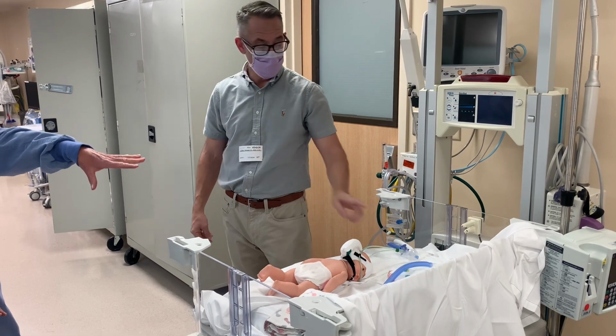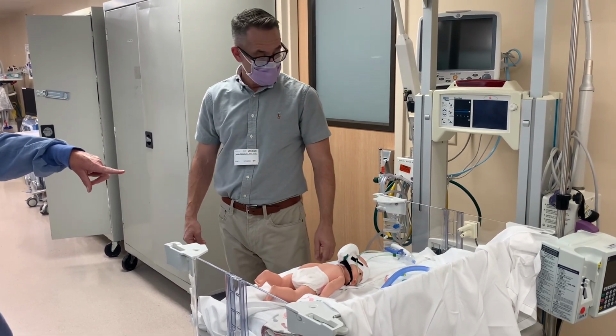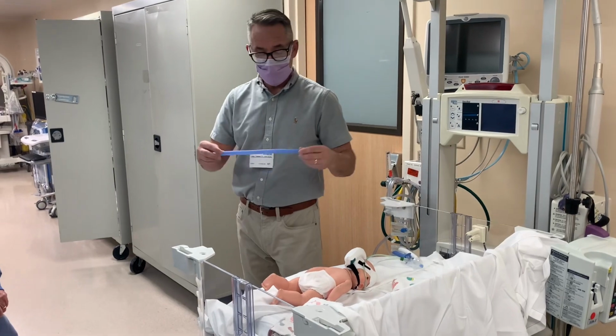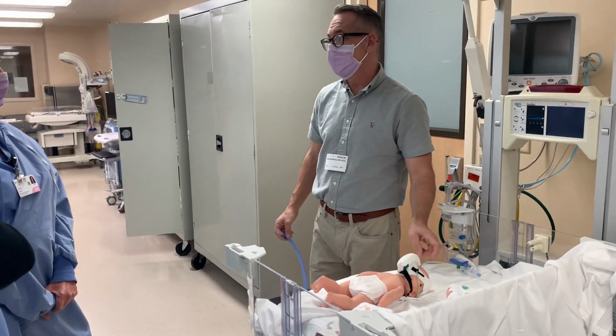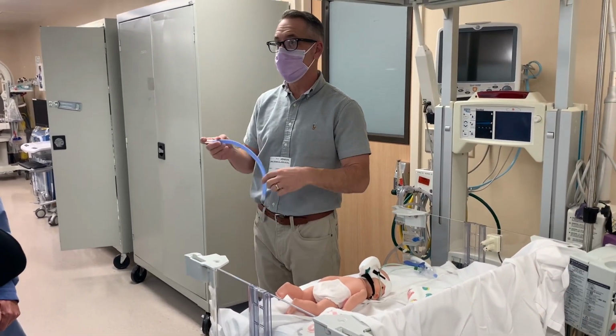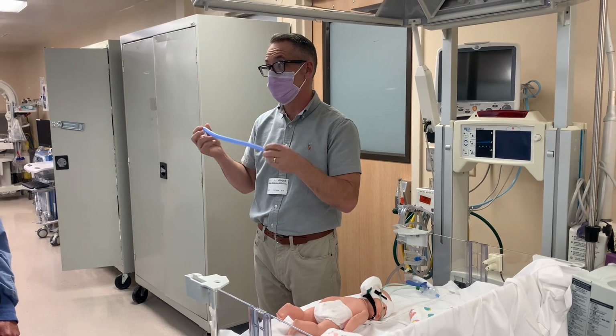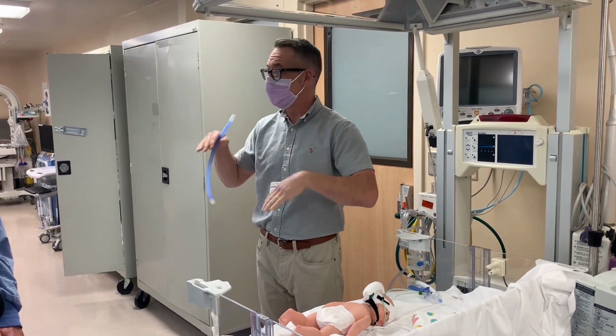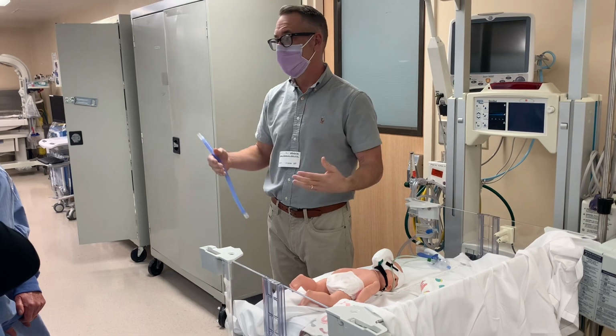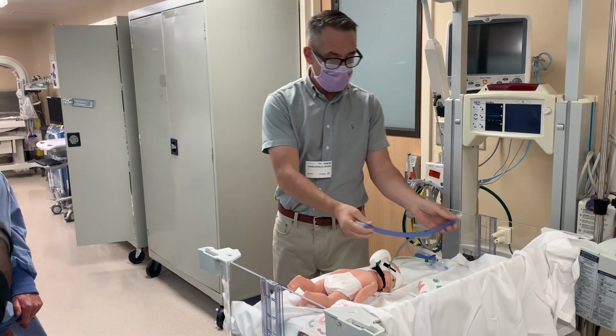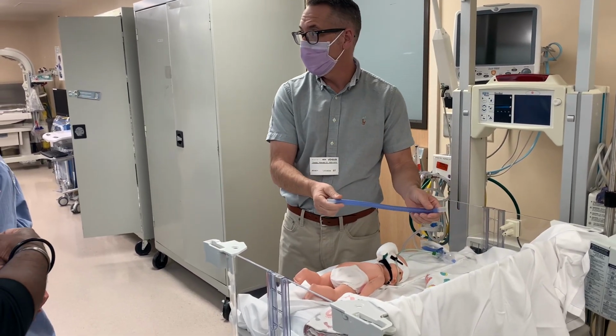Stable, baby. Stable, as opposed to the ambient air. So you always want to take that out. That's what you're recommending. Yeah, because you're using a cannula and that's already decreasing the temperature by potentially 5, and this is decreasing your temperature by potentially 6, that's 11. Whether it drops down to 11, there's some point where it's not going to go that fast, but still you're just creating a rainout machine when you combine the two together.